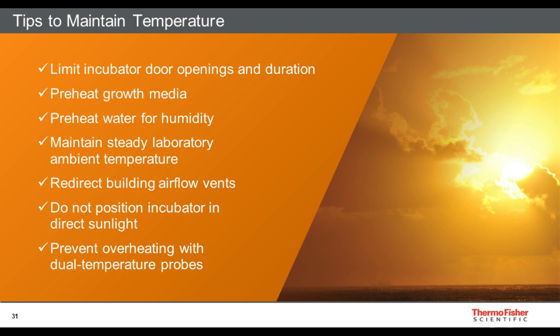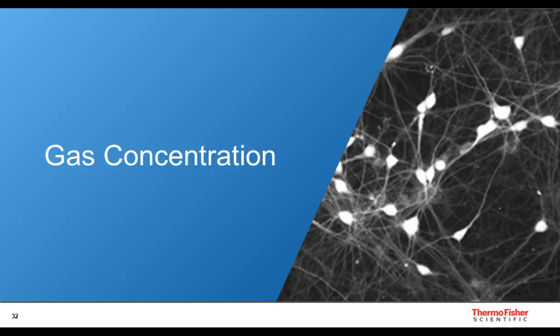I don't think this happens very often, but sometimes we all love to see sunlight coming into our workspace. So make sure that if you have windows such that sun is shining on the incubator, use window blinds to keep that sunlight from shining on it. And finally, if overheating is a concern for your incubator, one with a backup temperature probe helps prevent overheating in the event of a failure of the primary temperature sensor.